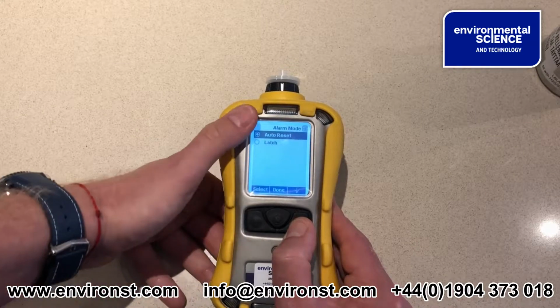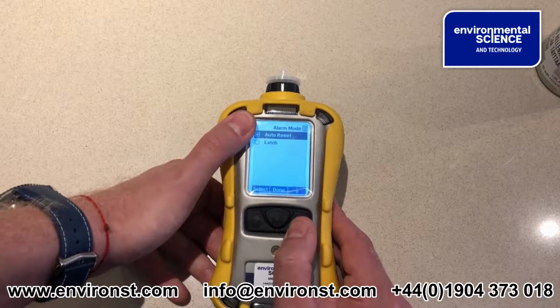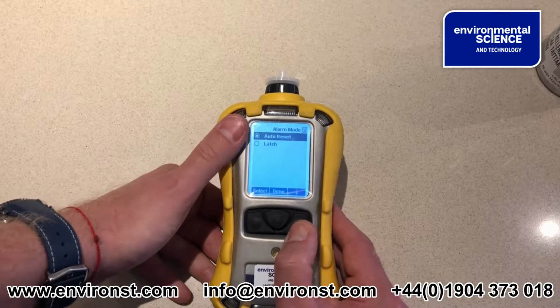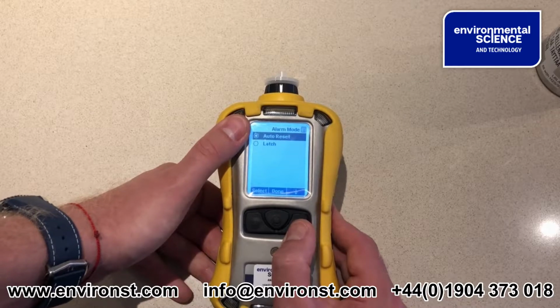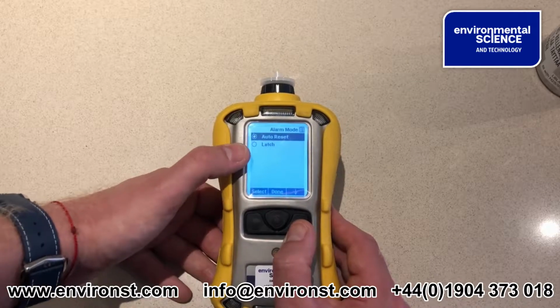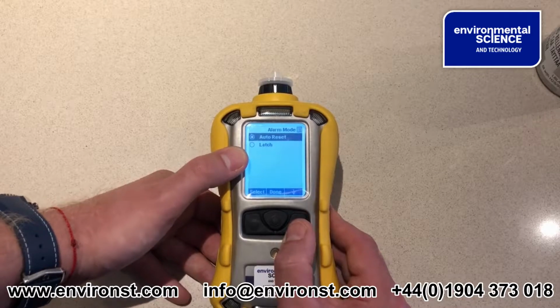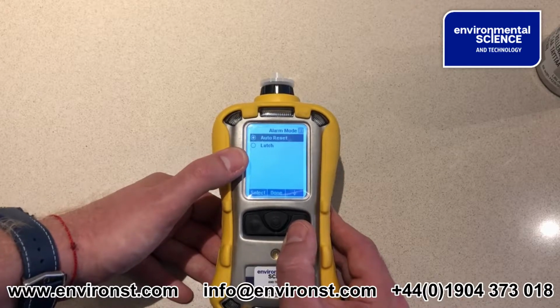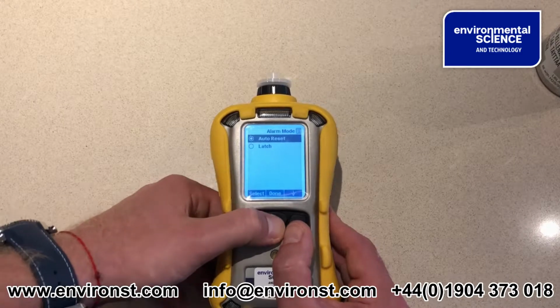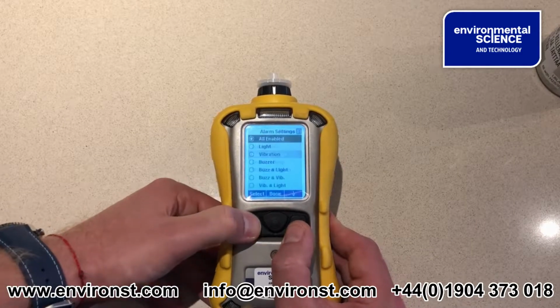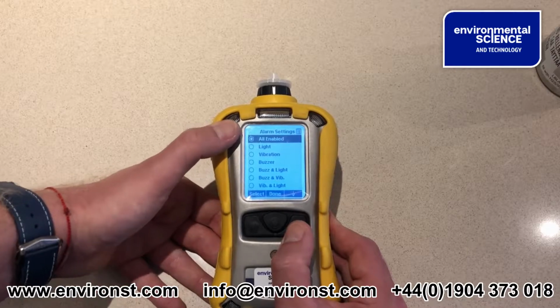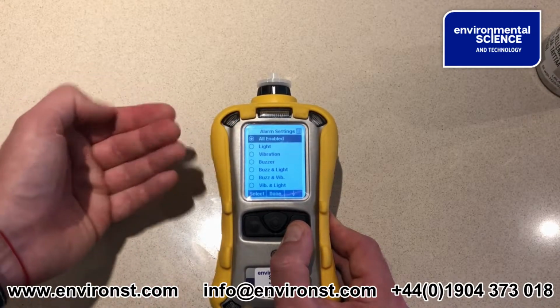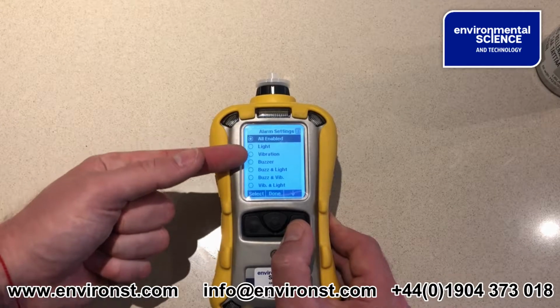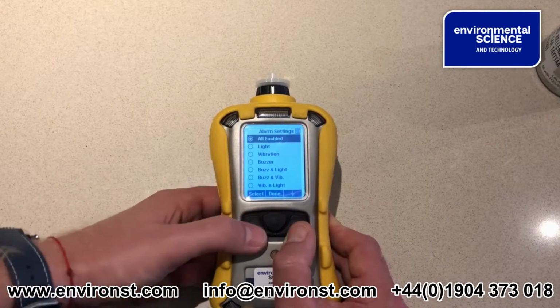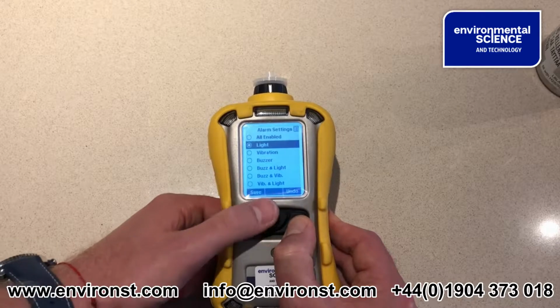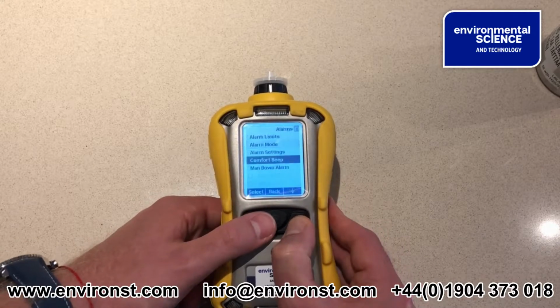Alarm mode, auto reset. So this is basically when gas goes above a certain level, it will go into alarm. When it drops back below a certain level, it will automatically cancel that alarm. Latching is essentially the instant it goes into alarm, you actually need to acknowledge it for it to be able to turn the alarm off. We're not going to touch those. Alarm settings. Now this is where you can have all features enabled, so all lights, buzzer and vibration, or you can select different combinations of below. And that's literally, you just toggle what you want. I'm not going to change those, there's no need.